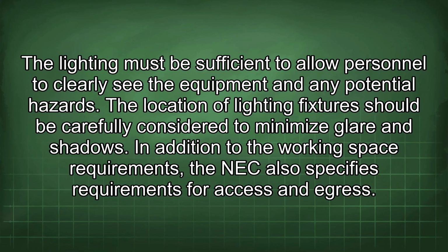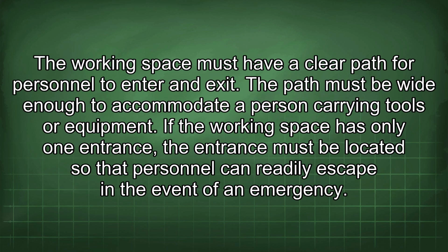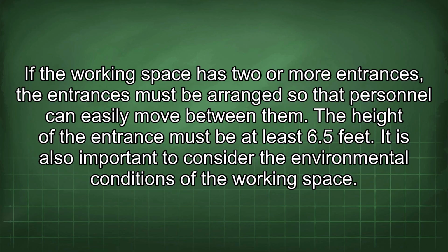In addition to the working space requirements, the NEC also specifies requirements for access and egress. The working space must have a clear path for personnel to enter and exit. The path must be wide enough to accommodate a person carrying tools or equipment. If the working space has only one entrance, the entrance must be located so that personnel can readily escape in the event of an emergency. If the working space has 2 or more entrances, the entrances must be arranged so that personnel can easily move between them. The height of the entrance must be at least 6.5 feet.